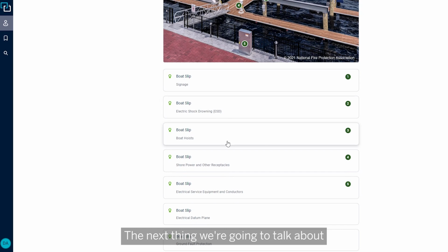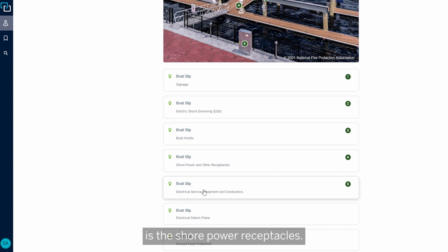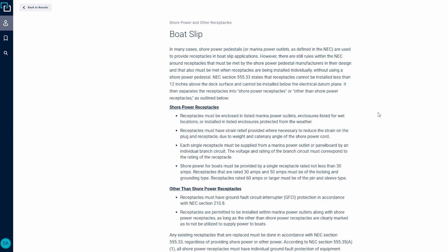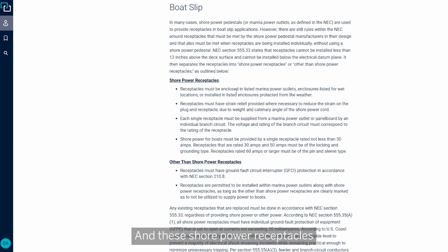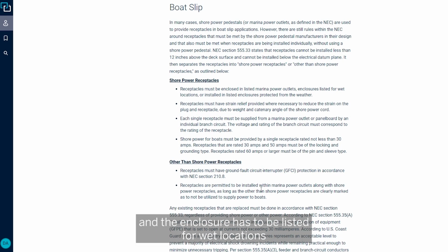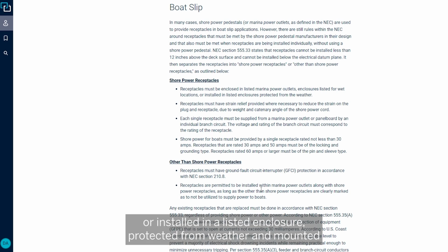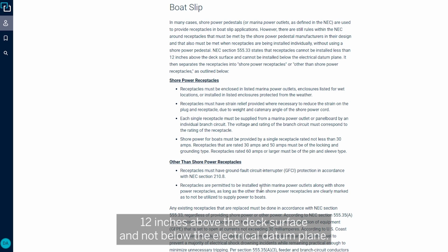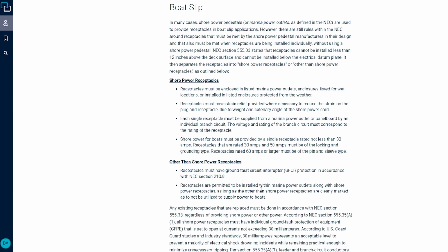The next thing we're going to talk about is the shore power receptacles. These shore power receptacles must be enclosed in a listed marina power outlet, and the enclosure has to be listed for wet locations, or installed in a listed enclosure protected from weather and mounted 12 inches above the deck surface and not below the electrical datum plane. We will cover the datum plane later.